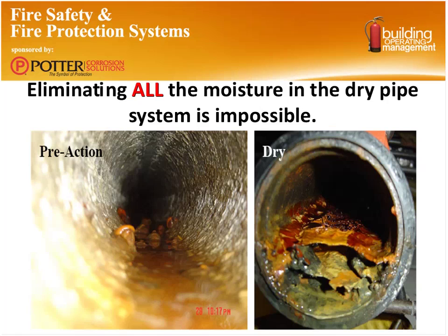So can you eliminate all the moisture in a dry pipe system? Well, that's probably not possible. If you're just putting air in a system, traditional compressed air, even with a dryer, there's a good chance that every time you put a little more air in that system, you're going to introduce a little more moisture into it. And as it condenses in that pipe, it's going to create water.